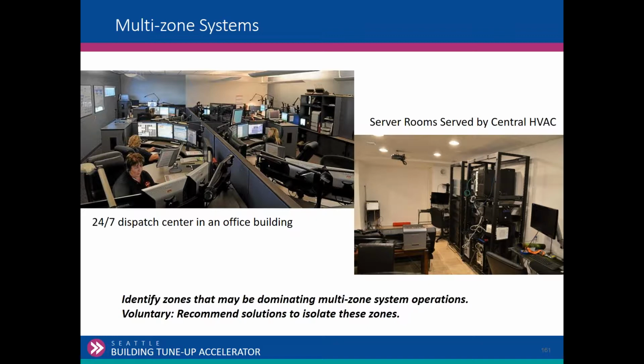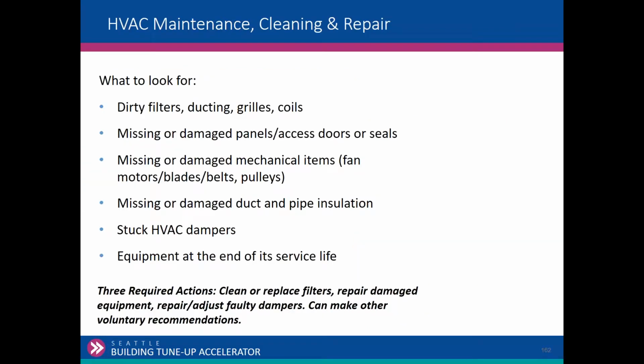There's an awful lot of systems out there that have the capability of reset but aren't doing it for a variety of reasons. We tried to address that in the code to try to get engineers to design their cooling loads for 60-degree air instead of 55-degree air, so we could still meet those loads at 60-degree air. Dispatch center in an office building, so they've got one floor that's 24/7. They're having to run their full chilled water plant, hot water plant, 24/7 just for this one floor or one zone. And I know that happens out there, and we have those instances, whether it's a data center on the floor or some tenant. But that's an opportunity if we can serve that with a separate system and shut that down. And then the last thing on the HVAC side is just general maintenance, cleaning, and repair.